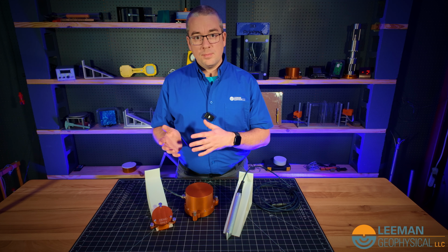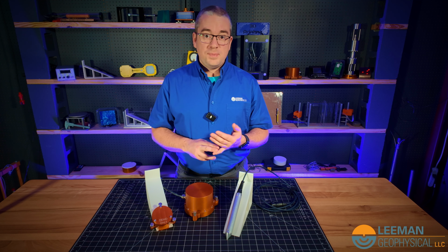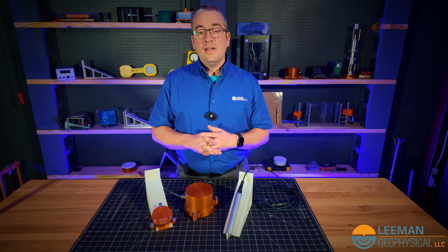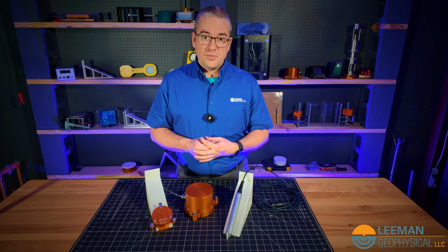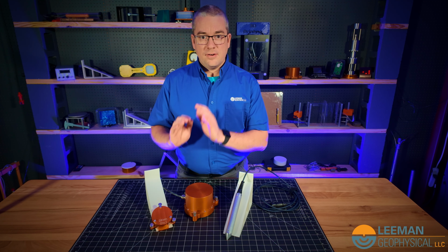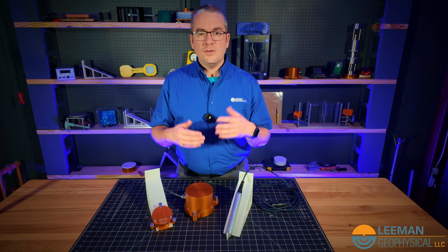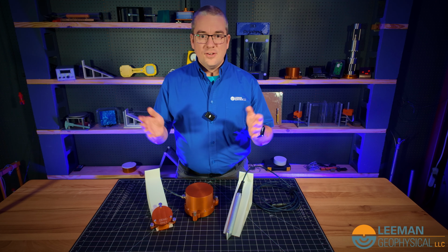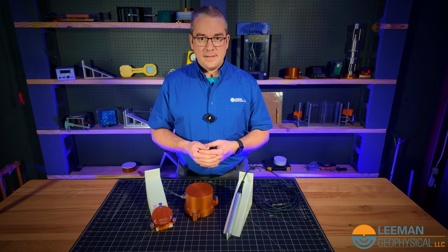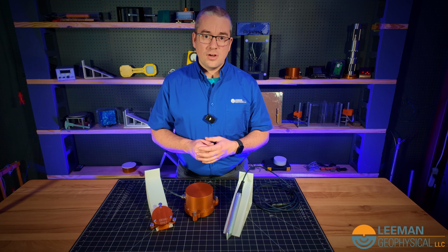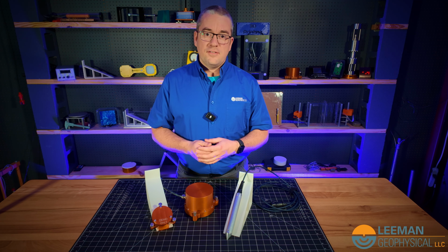If it's a short-term deployment and you value speed of deployment over maybe the accuracy of the instrument, then you can go with something like a MEMS surface inclinometer where you just connect a battery and everything's all set. All of the instruments are IP67 or better rated, so you don't really have to worry about them getting submerged in water or anything like that. But you do need to worry about things like protecting cables if they're going to be out for a long amount of time, or providing enough power.